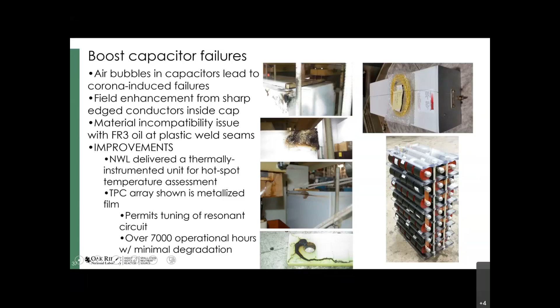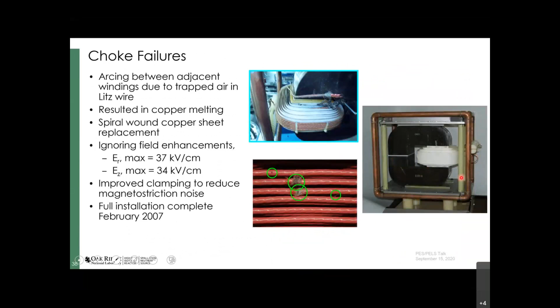Choke failures have been a problem again. The original design used Litz wires for obvious reasons. Unfortunately, the oil did not wick into the Litz wire very effectively. And so there were a lot of electric field enhancements due to the small diameter wires, and we had arcing occurring, and eventually they would fail and open up on us. We since went back to the same vendor that helped us with the transformer design and developed a spiral wound copper sheet winding for the choke, and that's actually been quite robust ever since.